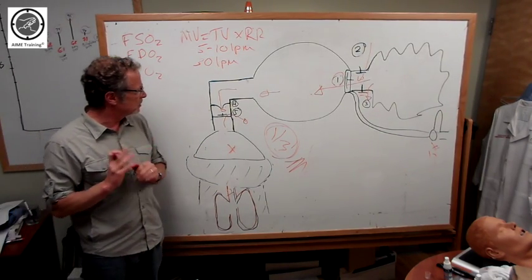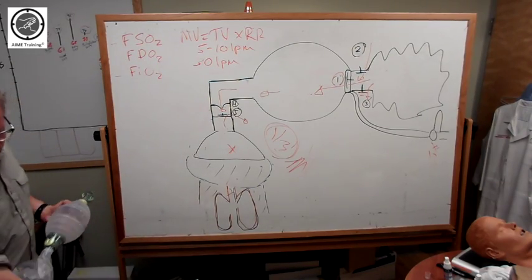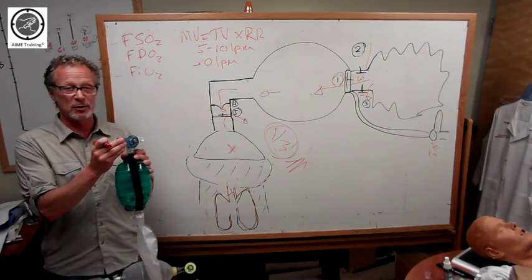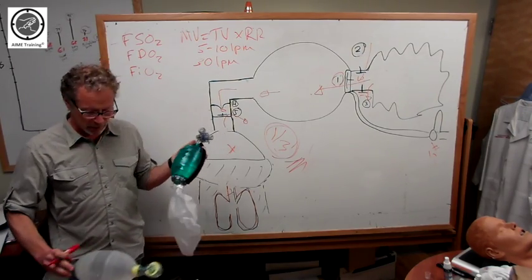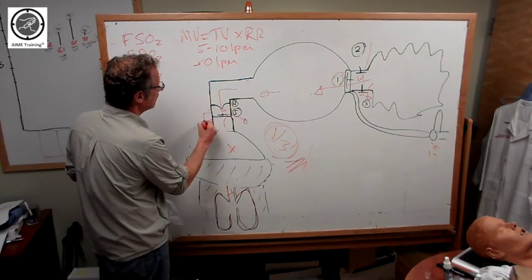The other important one to appreciate that may be apparent on some, in fact most of them there, is this one. And this is not a valve, but this is a port. And this is a port for attaching your PEEP. And this port usually comes off here.